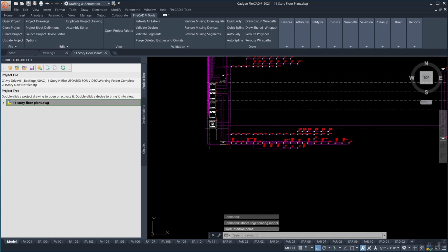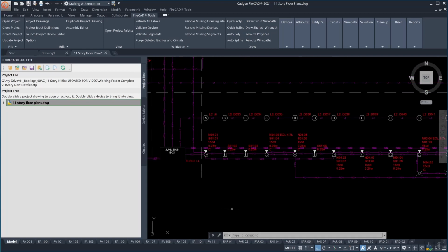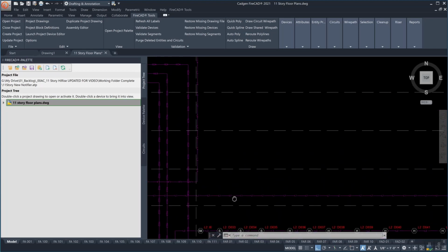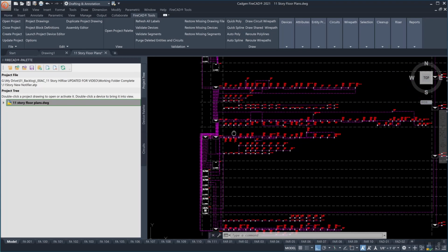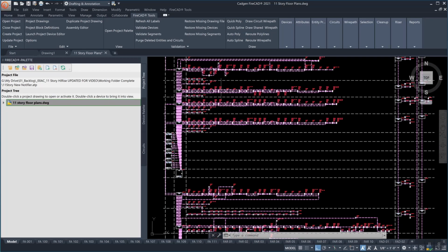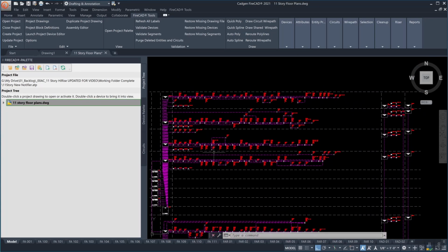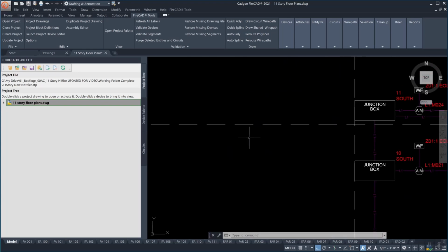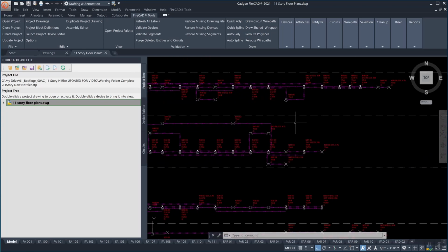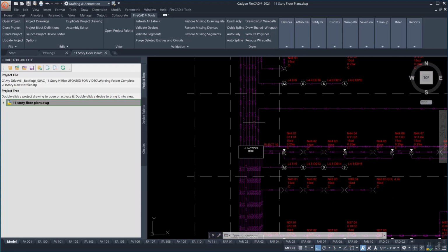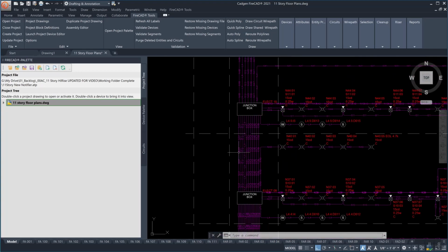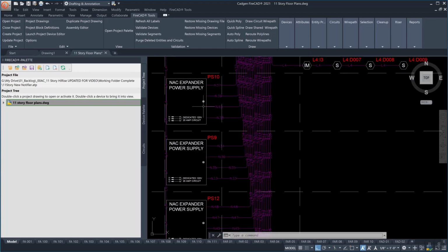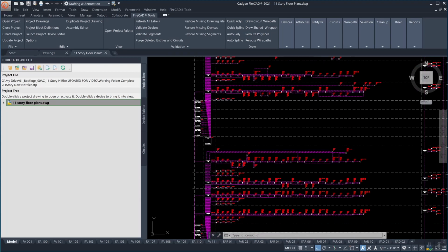And here's our final riser, showing all the devices on the elevations we want them on, the speaker circuits and NAC circuits connected to the speaker strobes, all separated out nicely. The riser showing the device elevations over here, the south stairwell riser with junction boxes, monitor modules, water flows, tampers, and all the control equipment and junction boxes neatly stacked up. That's the creation of the riser diagram.